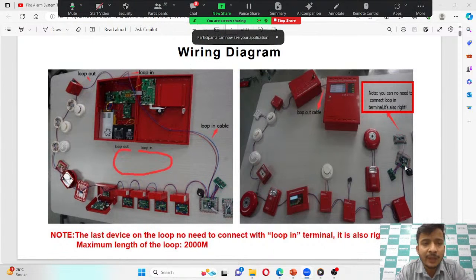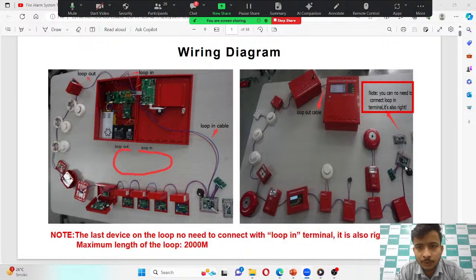As mentioned, this is the wiring diagram of our fire alarm panel. Both schemes are available in our fire alarm panel for wiring. As you can see, we have a loop in and loop out option, as well as an end of line option. In loop in, first you take a two core cable from the panel to the first device, and then from the last device you connect the two core wire again to the loop out port in the panel. This is the first option.